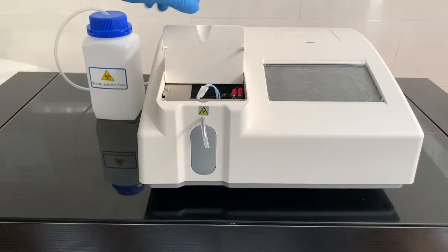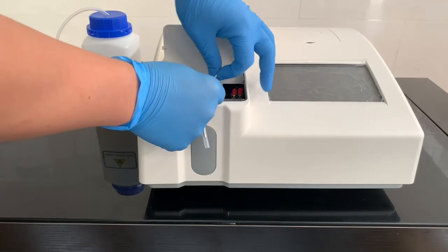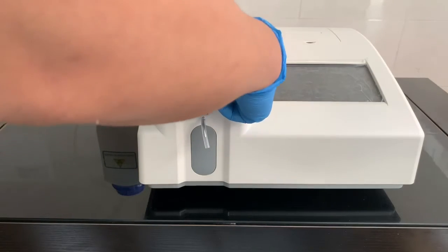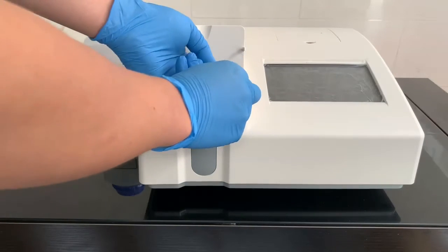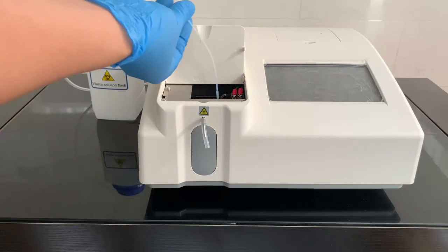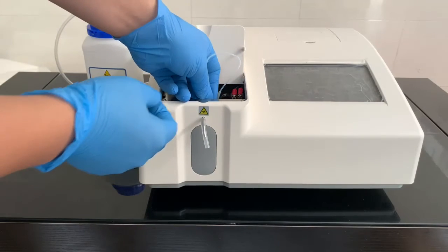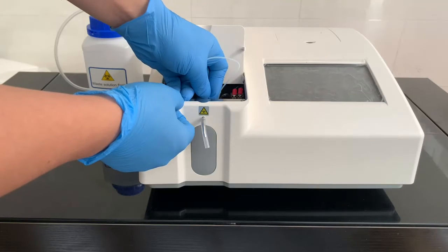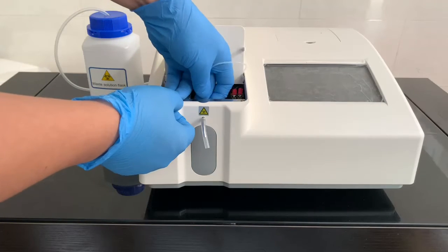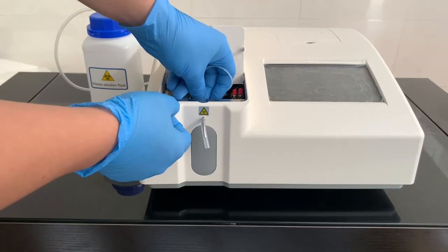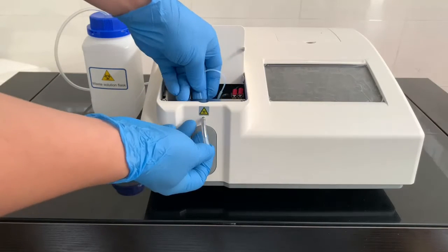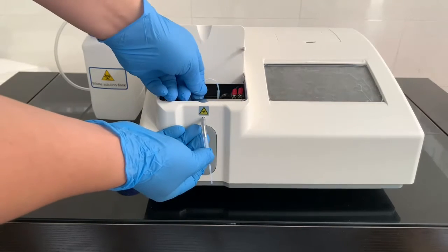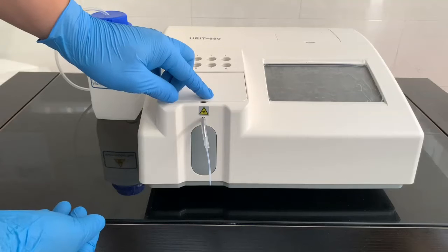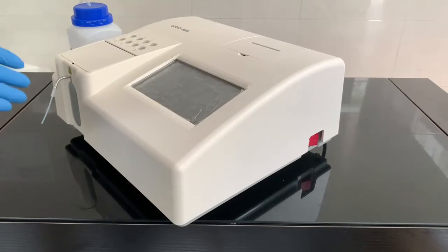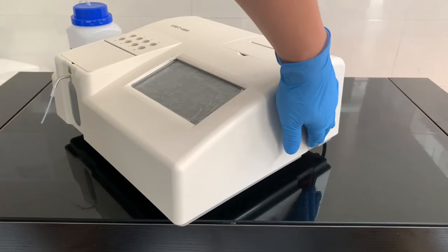Now we install the sampling tube. First, remove the tape. And release the tube. Insert the tube through the stainless tube. Adjust the length on the other side and close the cover. Check all the connections before we start. And if everything is okay, then we can start analyzer.